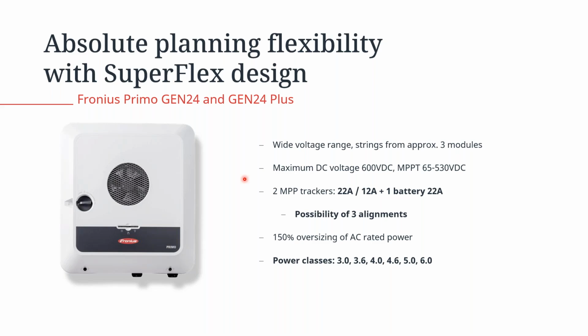In terms of the maximum DC voltage for the PRIMO inverter, the Gen24 and the Gen24 Plus, you can go to a maximum of 600 volts DC, but the MPPT operational voltage is starting from 65 to 530 volts DC. So both the Gen24 and the Gen24 Plus have 2 MPPTs. So the first MPPT can take 22 amps and the second MPPT takes about 12 amps. And of course, for the Gen24 Plus, you have an active battery connection that takes a maximum of 22 amps. So it means here you have the possibility for doing 3 alignments. So we look at this later.